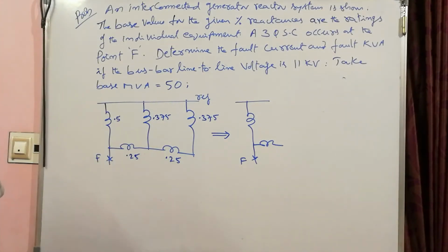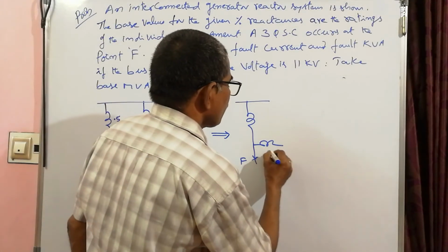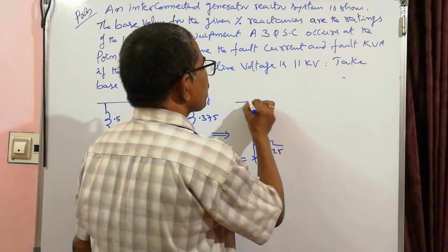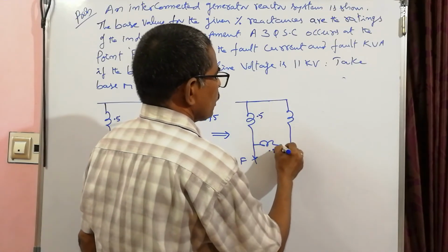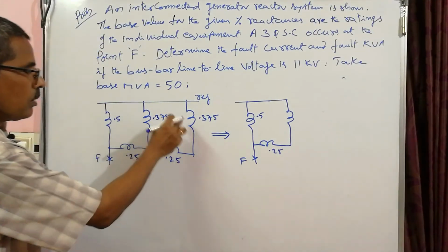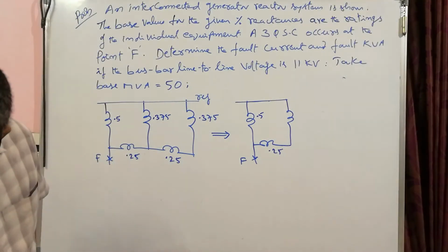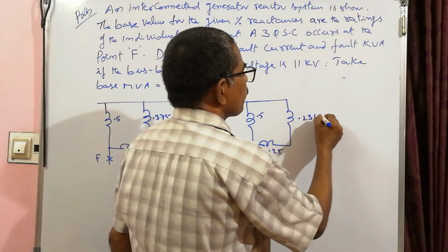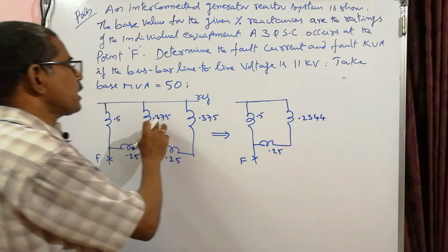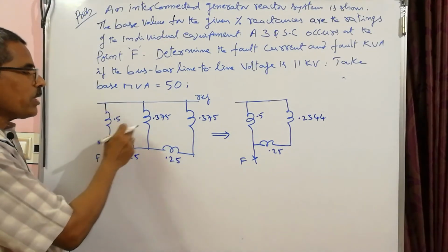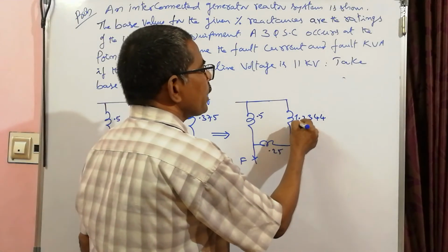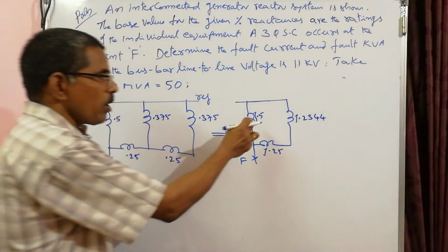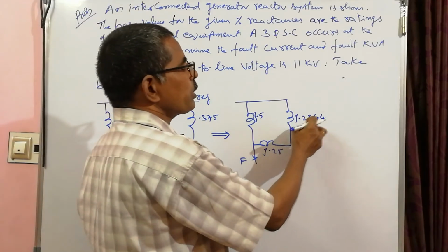So if I do that, this is 0.25, this is 0.5, generator 1 and reactor 1, and this equivalent, if I combine all this, that value is 0.2344. So even though we write this as 0.5, 0.25 and all, these are all with J's only, because these are all reactances. You are expected to add J. So J 0.5, J 0.25, J 0.2344.